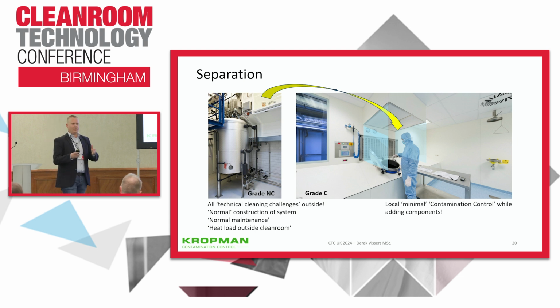You have the overpressure in your clean room. Okay. So the airflow is from the clean side towards the non-clean area. So the overpressure protects against incoming contamination. Mm-hmm. Will that be enough to reduce the risk? If you can maintain overpressure, there's no risk. But if not, then it's a potential. That will be in trouble, huh? Yeah. Okay. As long as you haven't...